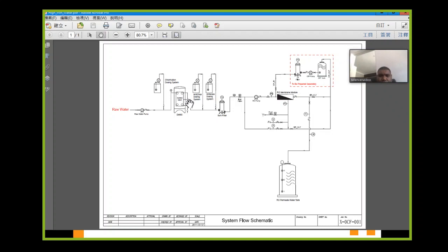And if you have too much chlorine, then you might need a larger dosage rate for the anti-chlorine dosing, or if you have carbon afterwards, then the lifespan of the carbon will be much shorter than you expected. Because if you just use carbon, how are you going to tell the free chlorine level at the outlet of carbon? How can you tell when the carbon becomes saturated?